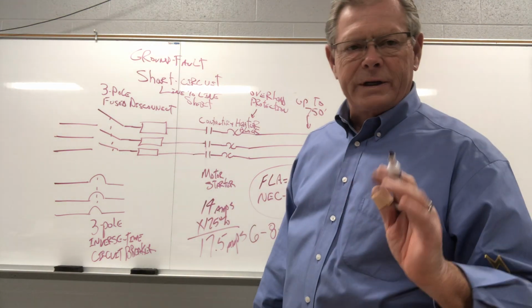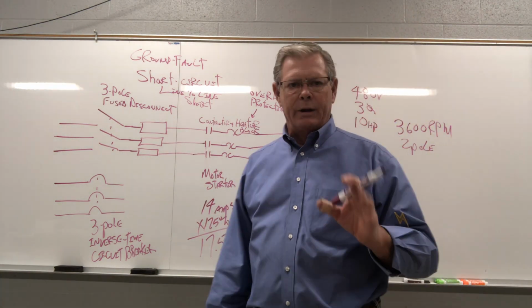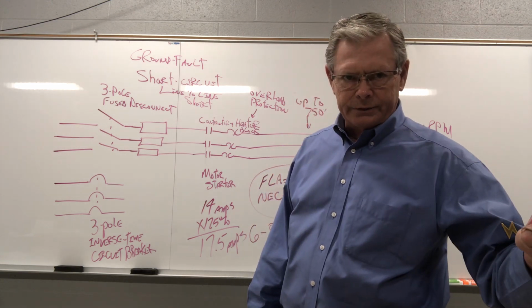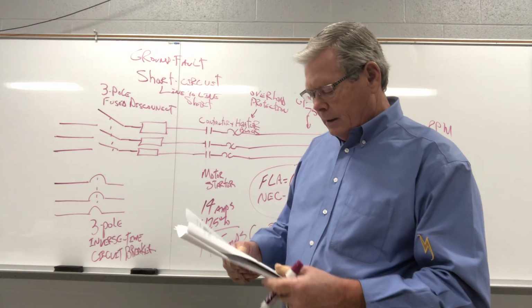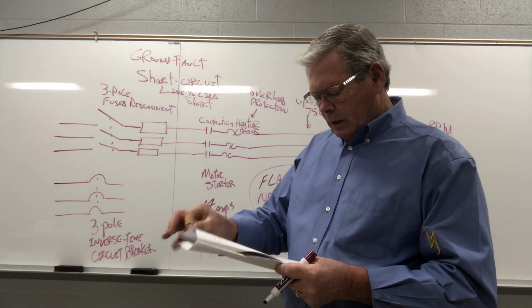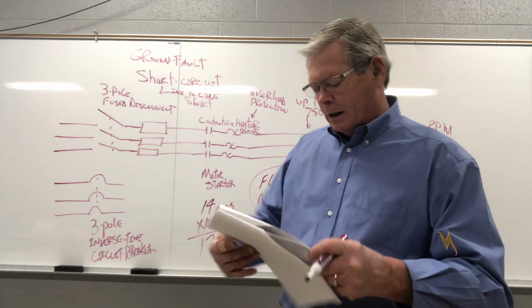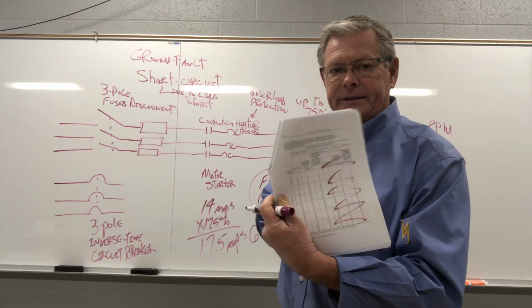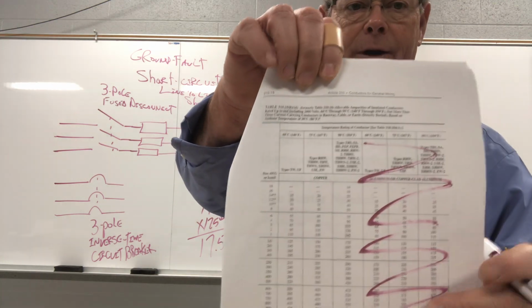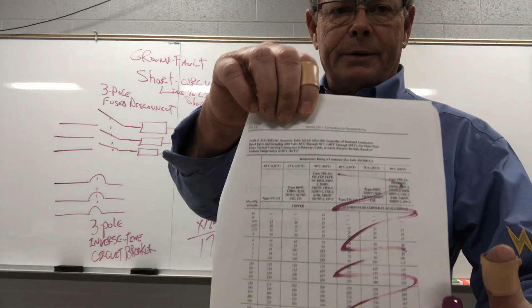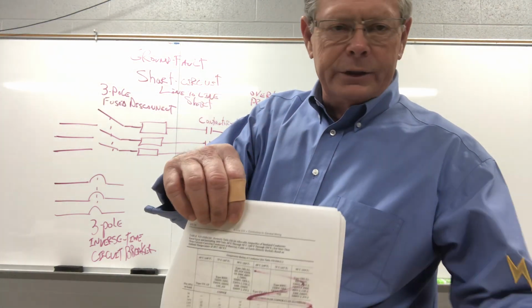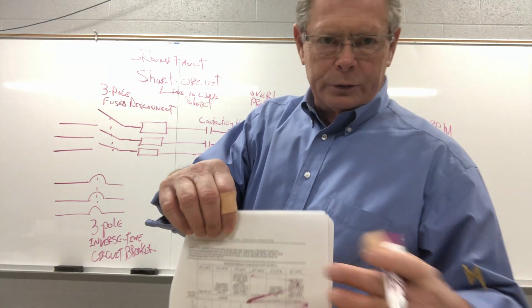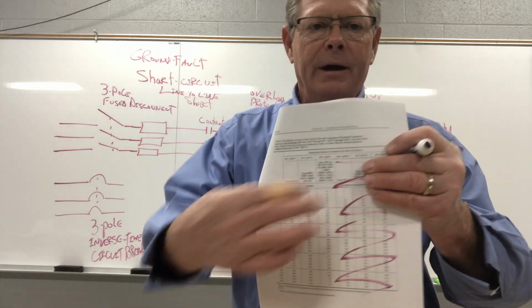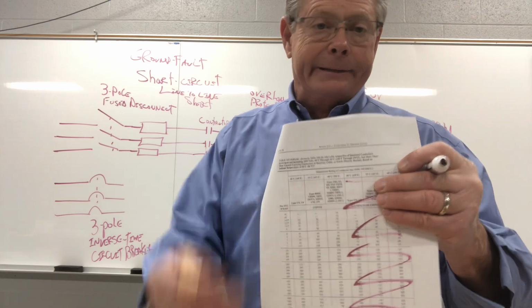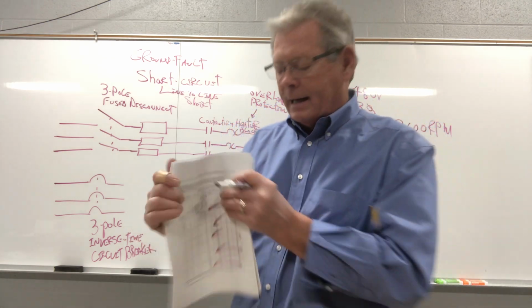The arrow says 14 gauge wire is the smallest wire we can pull into a motor in the real world. Okay? So we know 14 is the smallest. We're going to go to the next page. This here is our ampacity chart. This side here is aluminum. I mark it out. We're not using aluminum for motors in most cases. We're using copper, but I didn't mark it out so I can't use it. I just marked it out so it doesn't catch my eye.